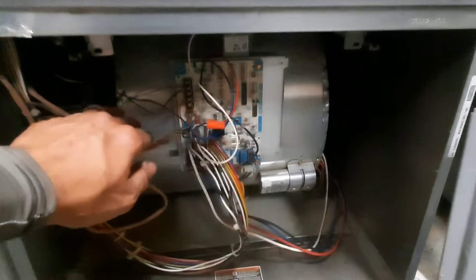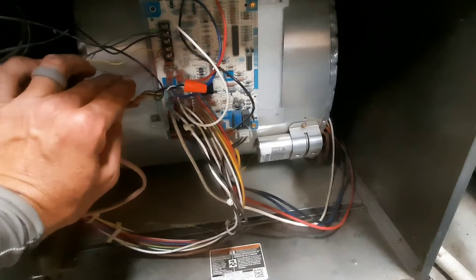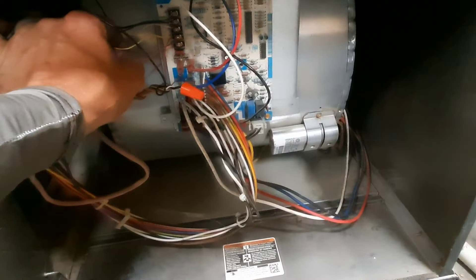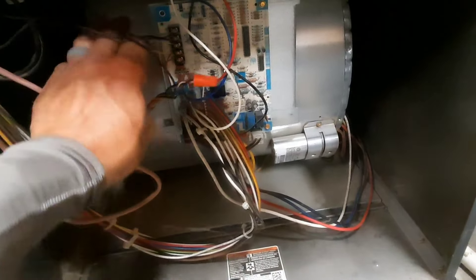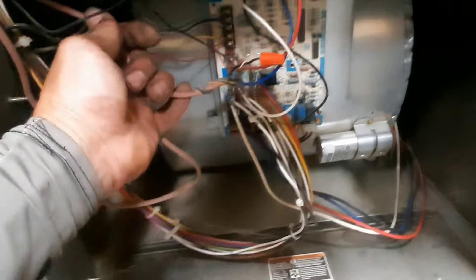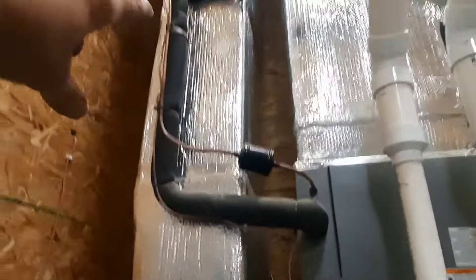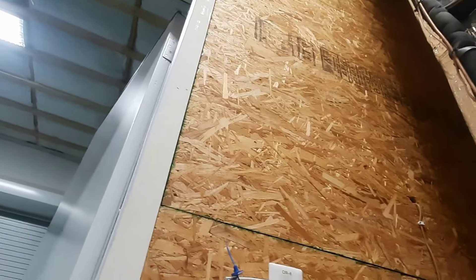Let's get a little jumper in here. It's gotta be in my yellow wire, could be going to the outdoor unit too. So we're gonna have to isolate and figure that out - I've got more wire if I need it. I didn't see anything noticeable outside but it runs all the way up with the line sets and it's all above a ceiling in an attic. I ain't going in the attic. We'll figure it out.